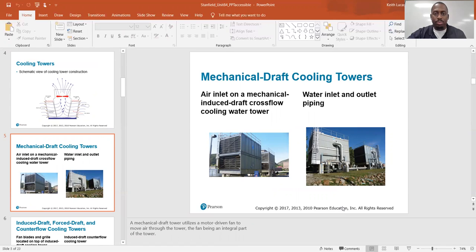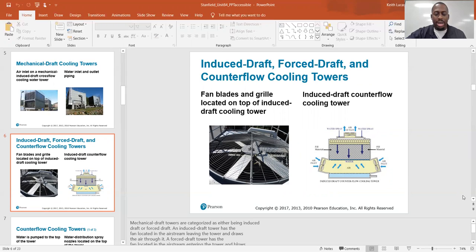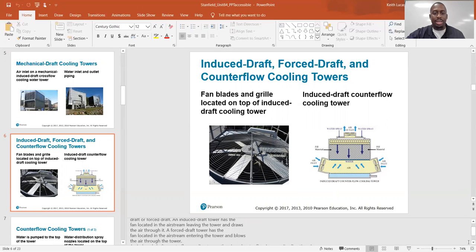Mechanical draft cooling towers. This is the air inlet on a mechanical induced draft crossflow cooling tower, with water inlet and outlet piping. A mechanical draft tower utilizes a motor-driven fan to move air through the tower, the fan being an integral part of the tower. Mechanical draft towers are categorized as either induced draft or forced draft. An induced draft tower has the fan located in the airstream leaving the tower at the outlet, and draws the air through it. A forced draft has the fan located in the airstream entering the tower, at the tower inlet, and blows the air across the tower.